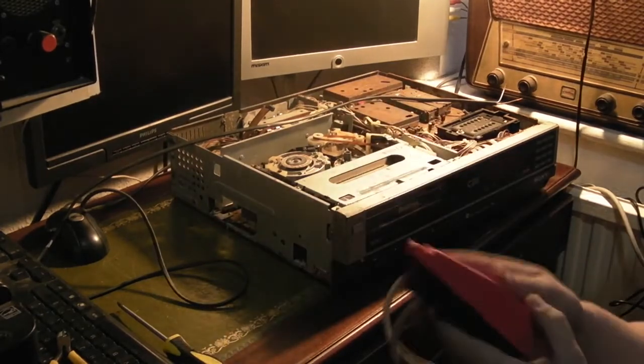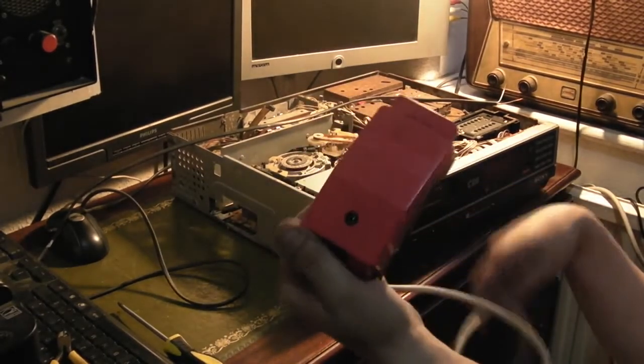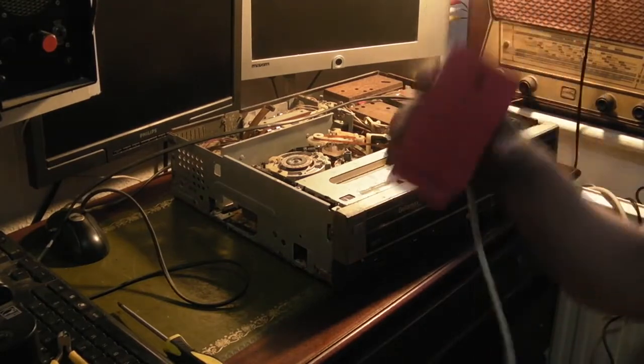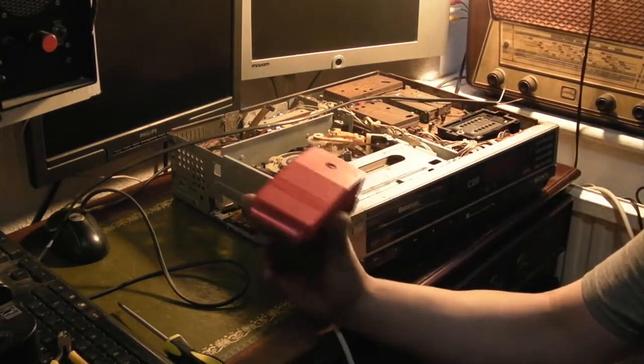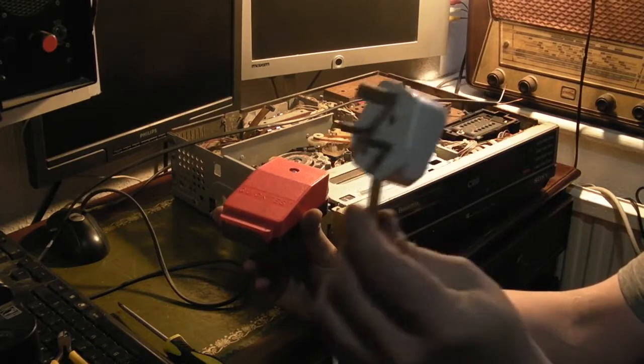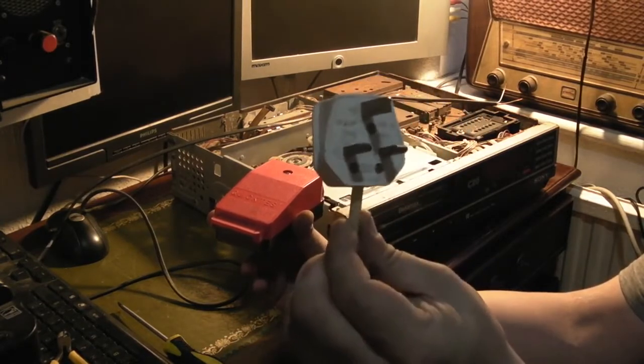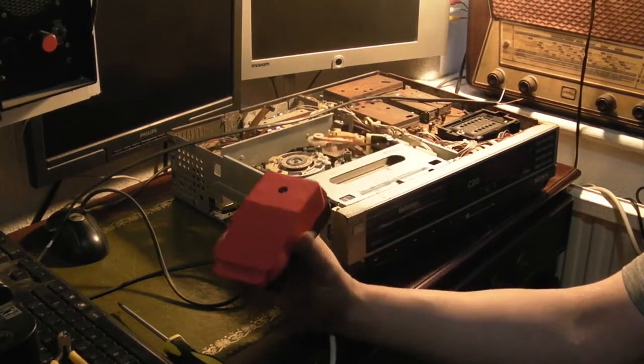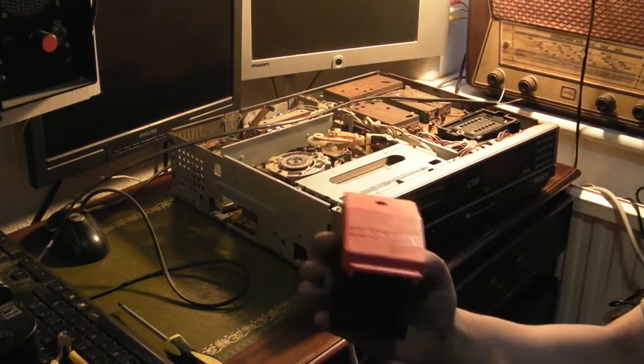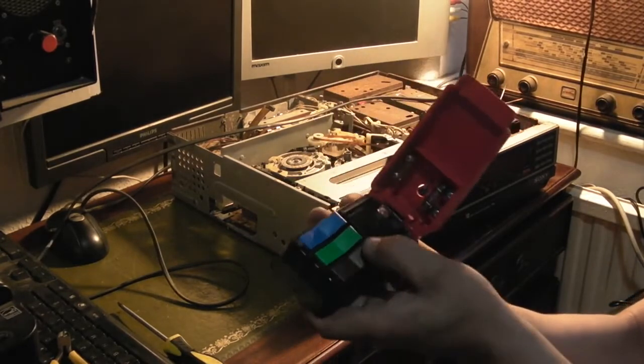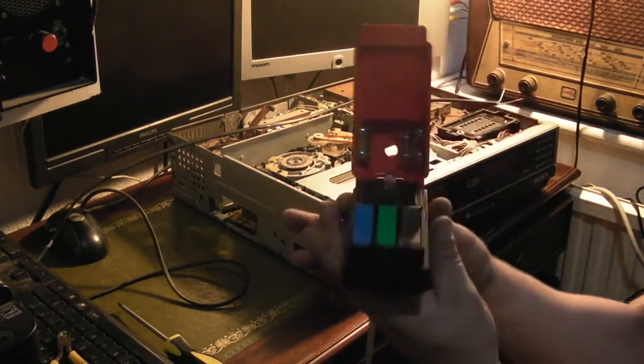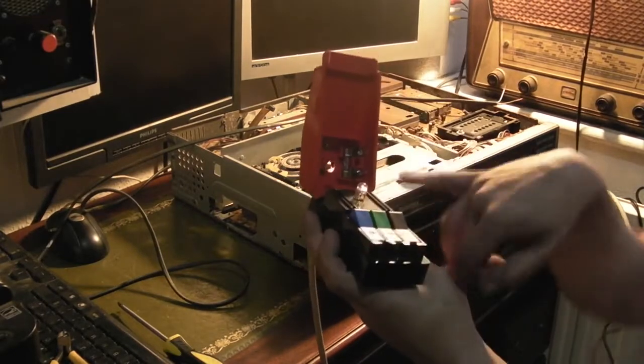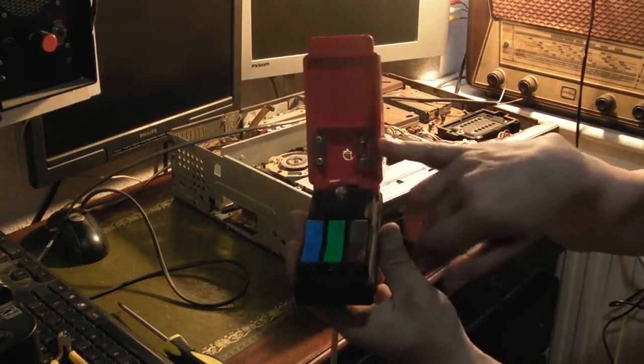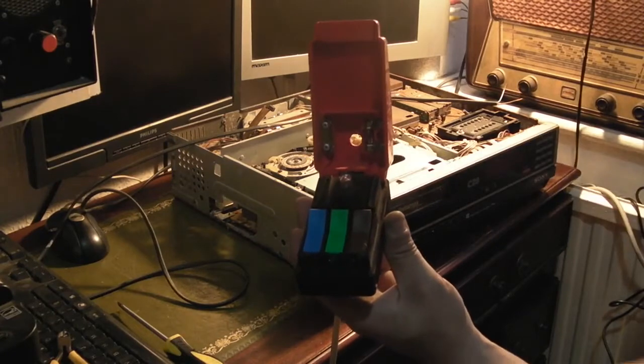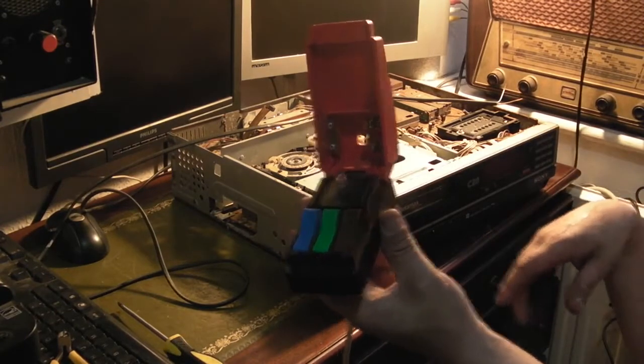I don't know if anyone has come across one of these before. It's quite a nifty little device for testing equipment that hasn't got a mains plug on it. We've got a standard UK 13 amp mains plug, though obviously for other countries you'd just have a different mains plug. Inside there are 3 sprung contacts and a safety lid with a fuse. This one has 13 amp in it, but you could fuse it right down to 1 amp if you wanted, depending on what you're working on.